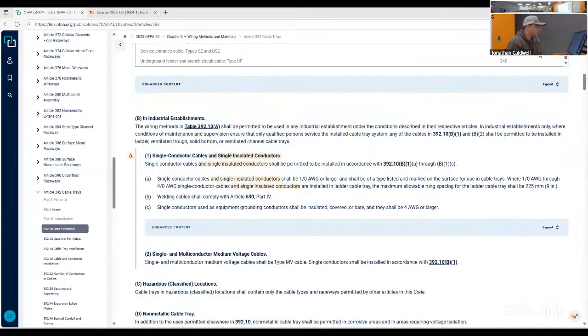Single conductor cables and single insulated conductors. Single conductor cables and single insulated conductor cables shall be permitted to be installed in accordance with 392.10(B)(1)(a) through (B)(1)(c). Single conductor cables and single insulated conductors shall be 1/0 or larger and shall be of a type listed and marked on the surface for use in cable trays. Where 1/0 through 4/0 single conductor cables and single insulated conductors are installed in the ladder cable tray, the maximum allowable rung spacing for the ladder cable tray shall be 9 inches.